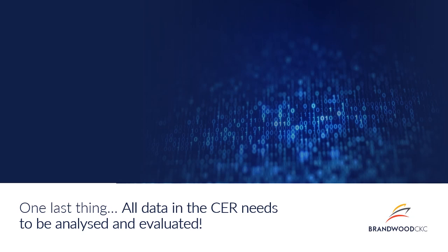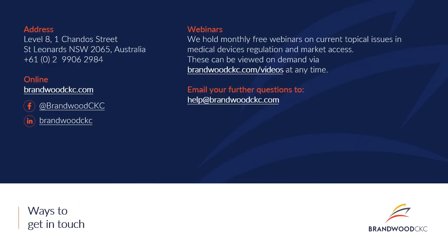One last thing, all the data in the clinical evidence report needs to be analysed and evaluated. This is probably one of the absolute most important points. It is not sufficient to simply present the data in your clinical evidence, just include your adverse events or your clinical trial data or your literature data. The key thing is to discuss, analyze and evaluate that data. What is the data saying about the performance and safety or the risk-benefit profile? Always bring that back to the purpose of this clinical evidence report. This is absolute key. Thank you to those of you who have sent in questions. I think I've covered many throughout my presentation today.